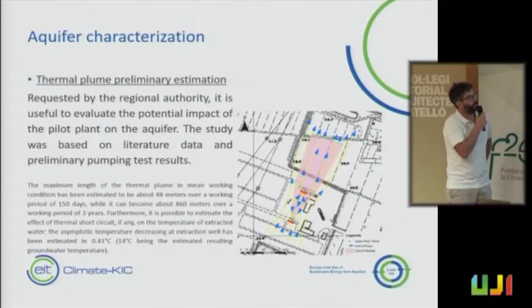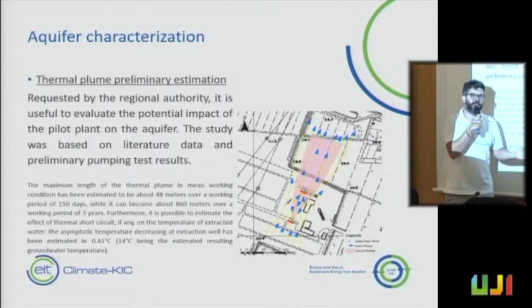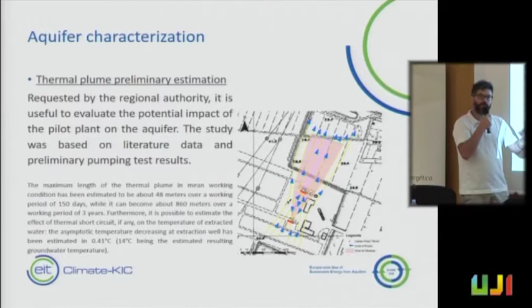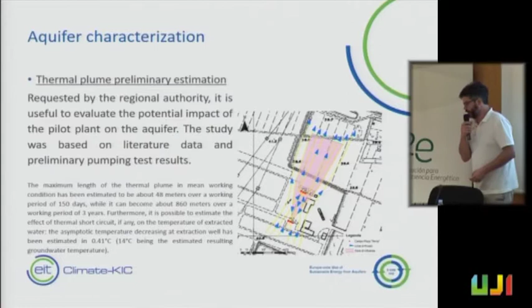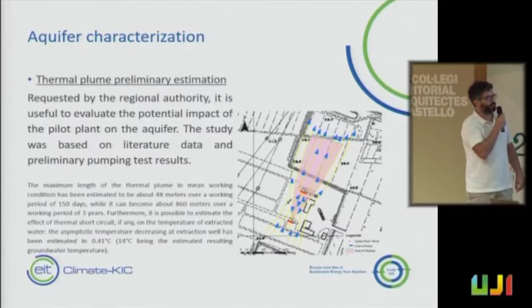Another thing that was requested by the regional authority was a study of the thermal plume. The thermal plume is a sort of temperature variation produced by the plant when it is in operation. Obviously, you take the groundwater and exchange it, so in winter you cool down the aquifer, and in summer you heat it up. So you have to consider, year by year, the effect of this heat exchange, and be sure it does not produce unexpected problems. So the region asked us to realize this kind of study, made by a geologist, starting from the information of this pumping test and taking into consideration data coming from literature.